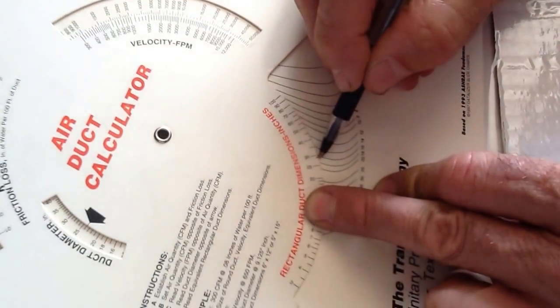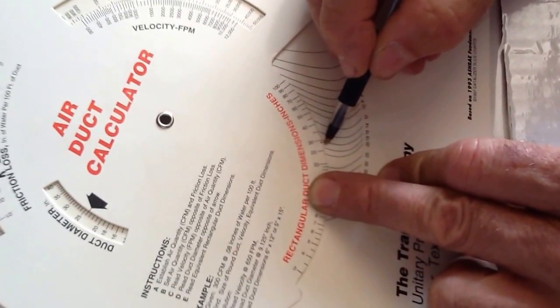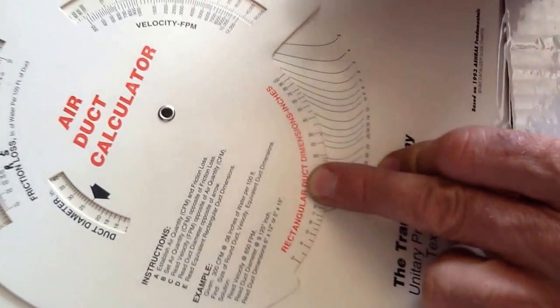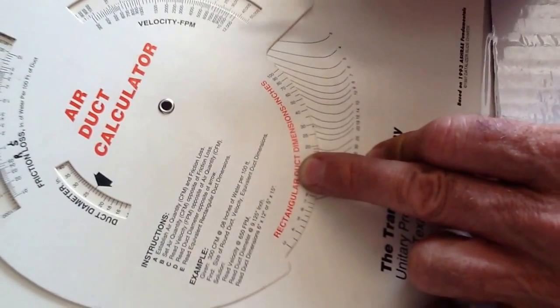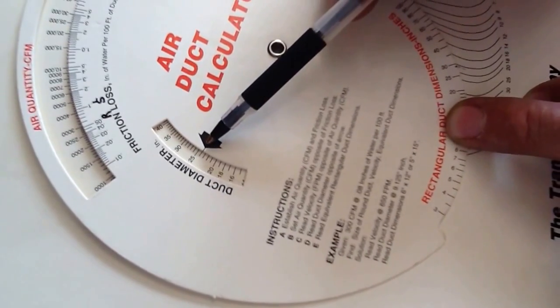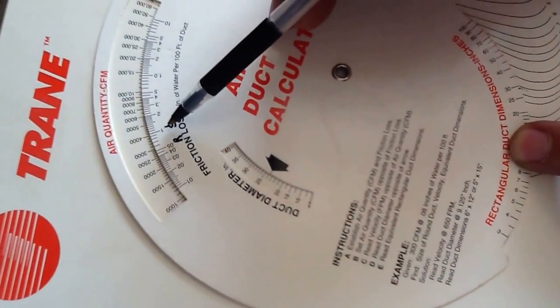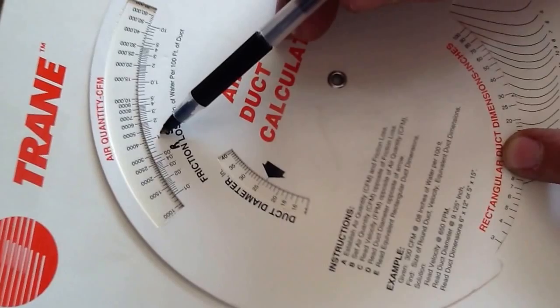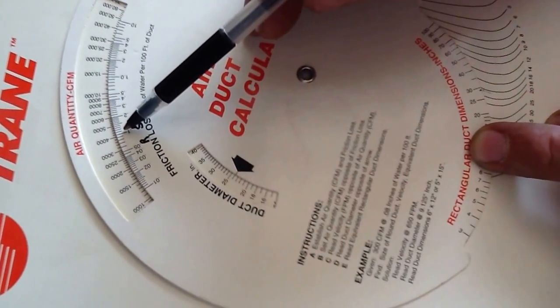So that's going to be like 29 by 17 right there. What size round duct do I need? I would have to have a 25 inch round duct. And that particular piece of duct work would supply 4,000 CFMs.